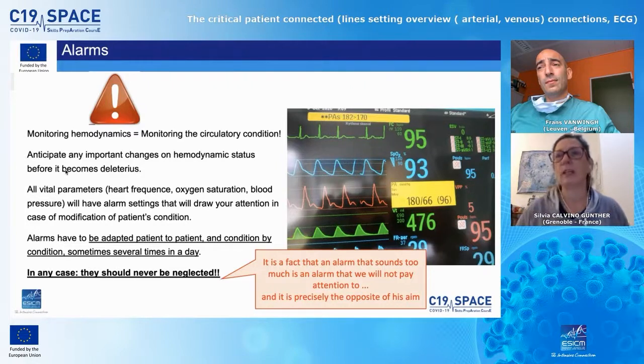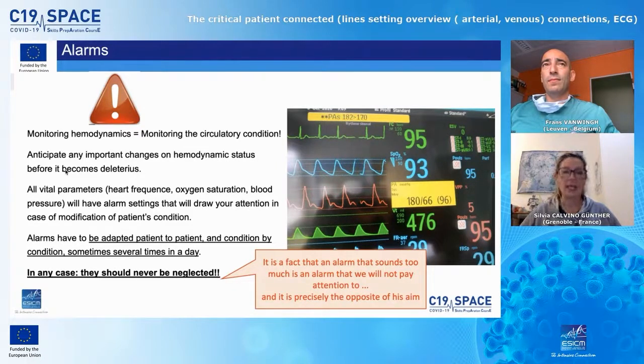We have already talked about the normal heartbeat from 60 to 100, but you have to think that in intensive care units, many times you will have abnormal numbers. So you have to adapt your alarms to these numbers and to the condition of the patient. It's a fact that an alarm that sounds too much is an alarm that we will not pay attention to, and in any case, that's precisely the opposite of its aim. In any case, an alarm should never be neglected.